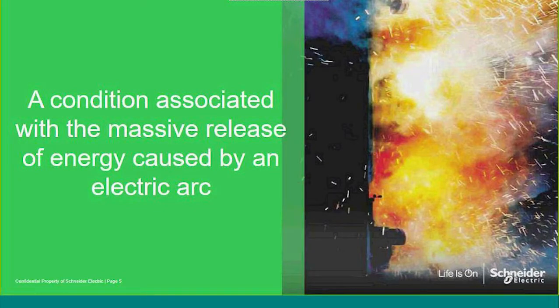So arc flash, what is it? Well, clearly, as you can see, hopefully from the screen in front of you, it is a massive release of energy. In fact, the arc flash classification is incident energy levels, and we talk about it in calorific values. So it's joules, basically, of energy. And that energy is released in many instances, sometimes in a controlled environment, so inside any piece of switchgear, whether it's medium voltage, low voltage, or even your domestic circuit breaker at home, has a controlled arc inside it. It's just that it's controlled. It normally is dissipated by a series of arc chutes, which break down the arc and the energies, and normally the energy is dissipated in a safe manner. However, you can't always guarantee that because you don't know where the nature of the fault may occur in your piece of electrical equipment, which means you could have an uncontrolled release of energy, and that's classified as an arc flash.